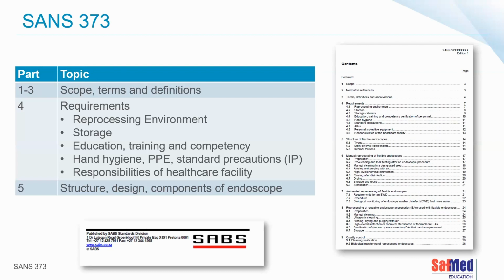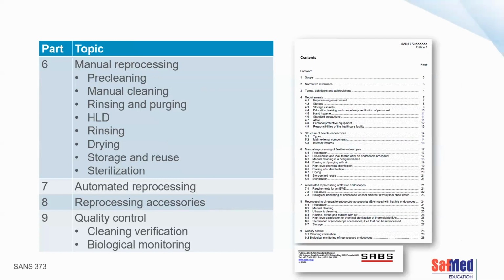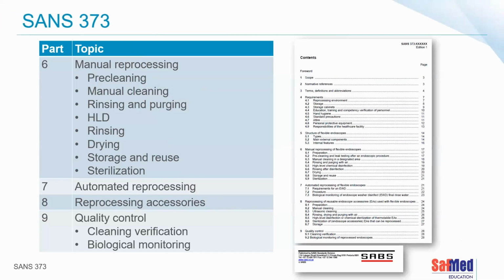Part 4 talks about the requirements. I'll go into a few points on that just now. Part 5 talks about the structure, design, and components of an endoscope, with a few diagrams to make it easier to understand the structure. Part 5 wasn't changed or adapted in any way; that stayed exactly the same. Part 6 then goes on to describe manual reprocessing, Part 7 focuses on automated reprocessing, Part 8 focuses on reprocessing of accessories, and Part 9 focuses on the quality control aspects - so that's the cleaning verification and the biological monitoring.